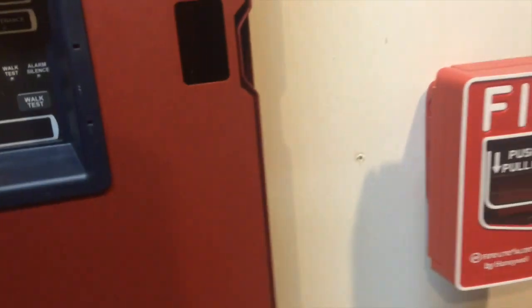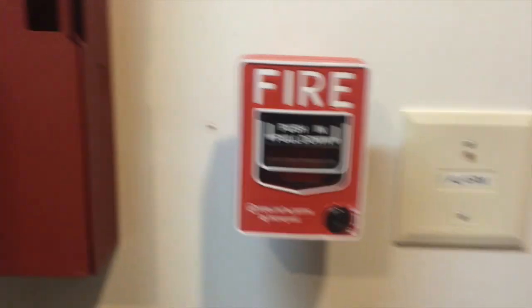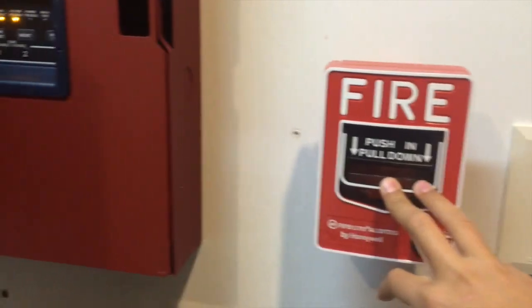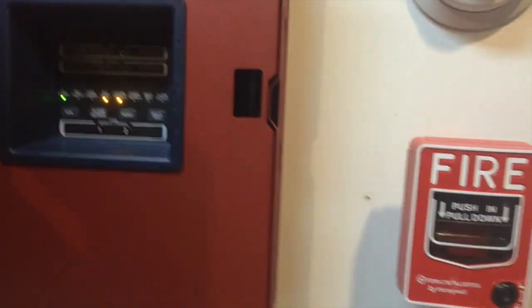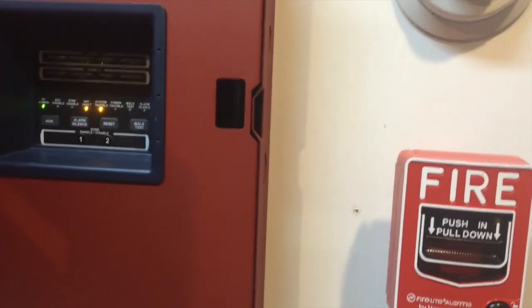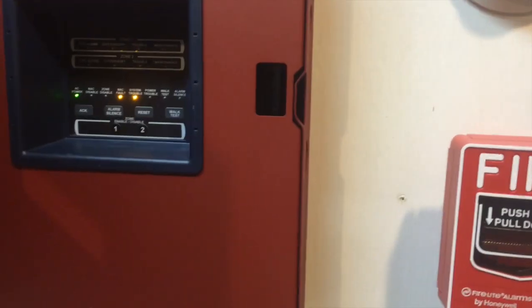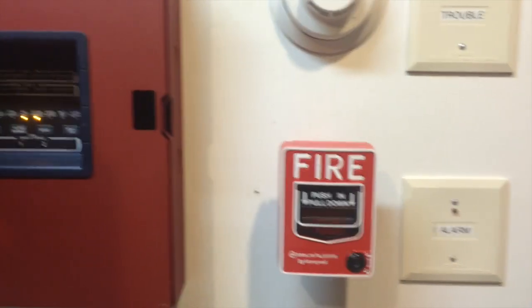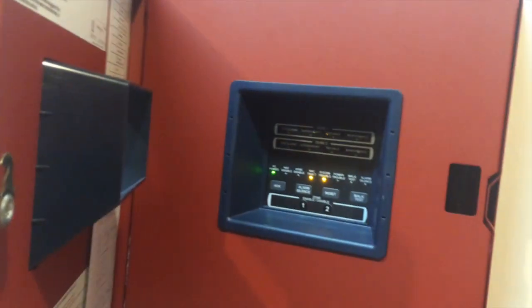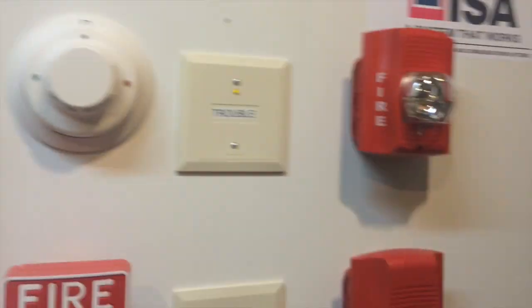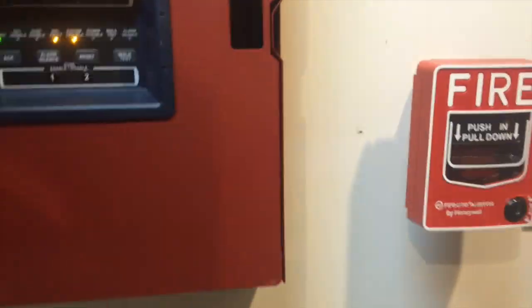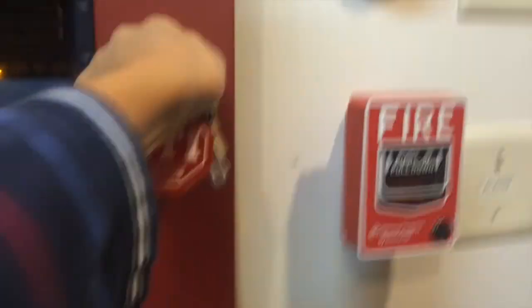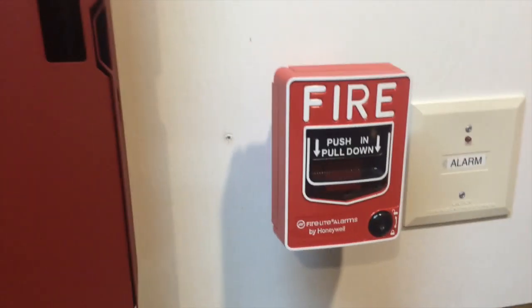So, I will pull this, and the panel will wait about 20 to 30 seconds, just asking the pull station, are you really pulled? Are you really pulled? And then, after about 30 seconds, it's going to say yes, and the panel's going to say, okay, I'm sounding the alarm, and it's all going to go off. And this is set on Code 3, low volume. So, here we go.